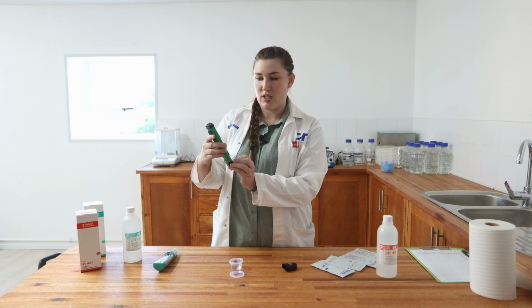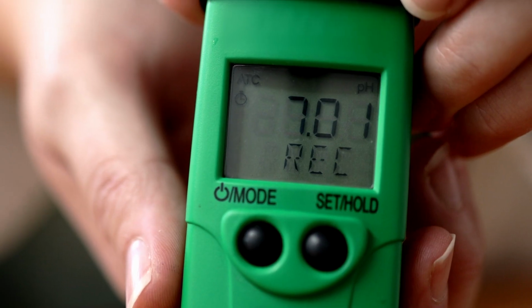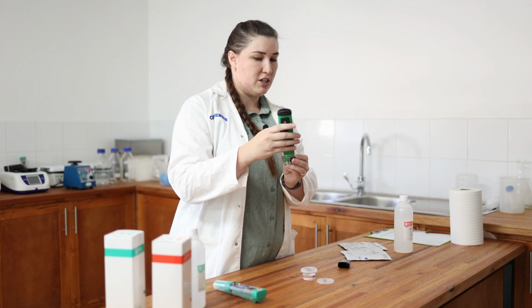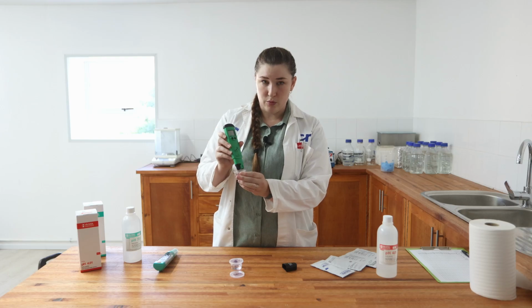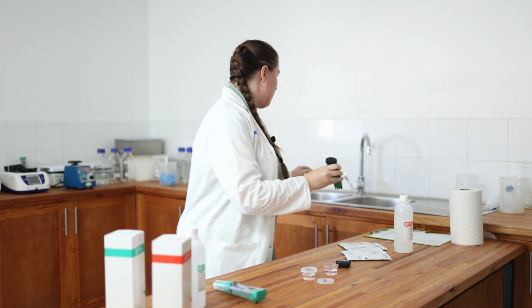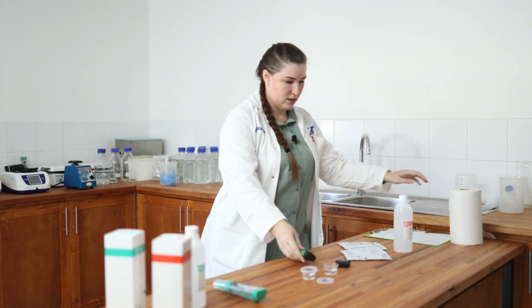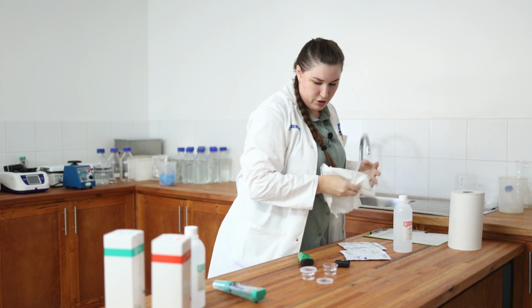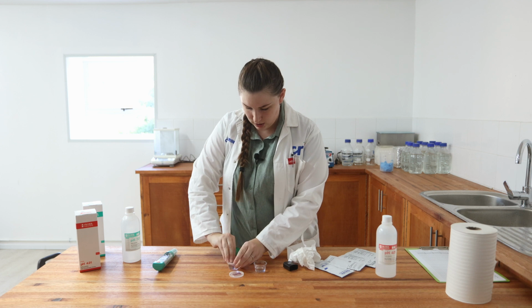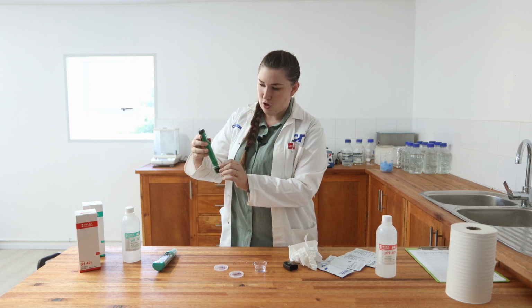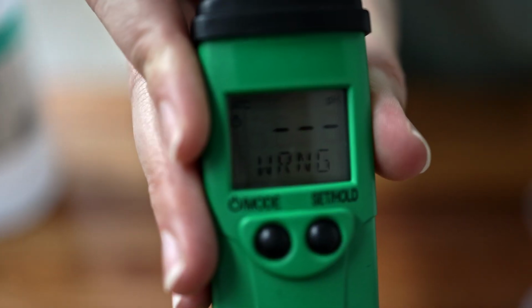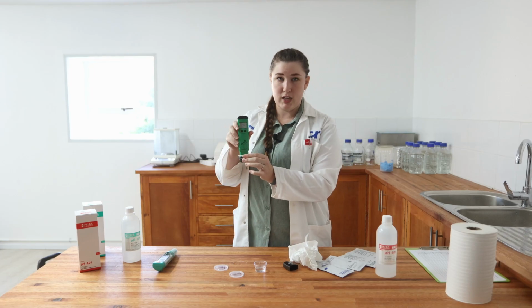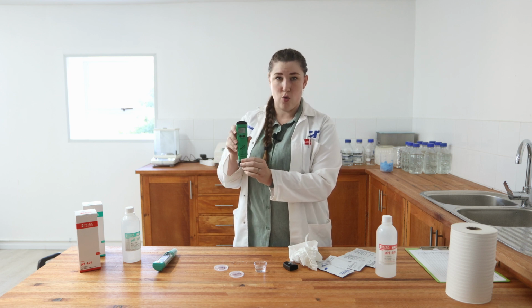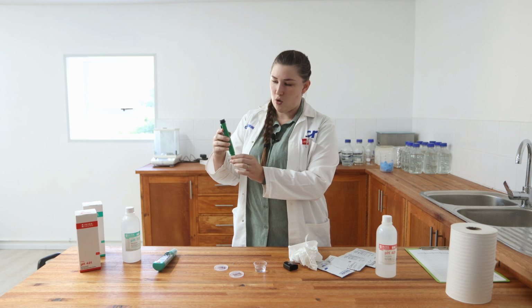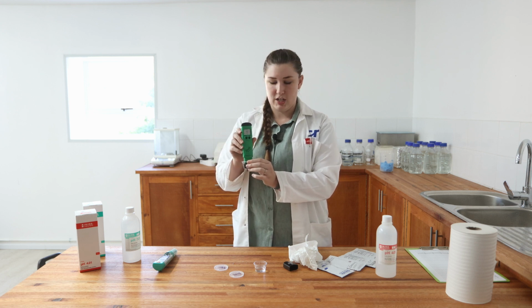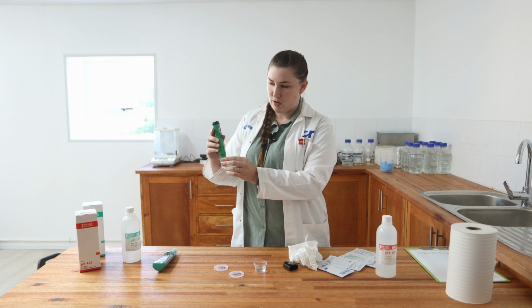So we just wait the whole time while it says record, and there is in this corner a small little calibration icon flashing, just so that you know that it's busy working. When it's done, it will move automatically to pH 4, and it will say 401 use. You need to quickly rinse it off, dry it so that you don't dilute your next buffer, get your pH 4 ready and put it in. If you're not quick enough, it will message wrong. So it's a good idea to have your tissue paper prepped and everything. But if you're quick enough, it will automatically go back and start recording at your pH 4. So here again, it's saying 401, record, and the calibration little icon is flashing. You just wait again while it measures and records that.